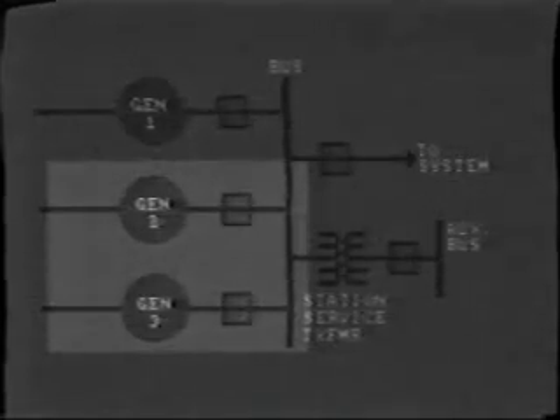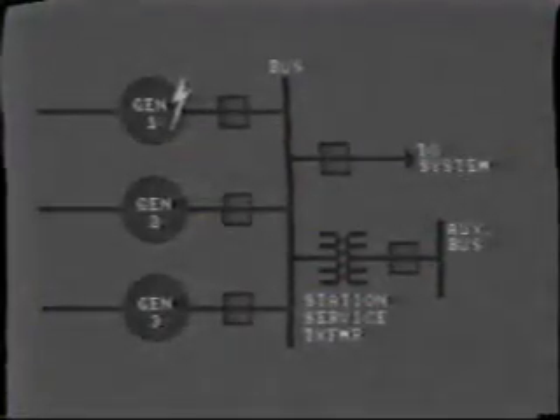Smaller generators are generally connected through the circuit breaker directly to a common bus. Several other generators may also be connected to this bus. The bus feeds the power system and also supplies the station service transformer, which provides power for the station auxiliaries. A fault occurring internally on generator 1 should be detected by its protection system, and this will cause its specific breaker to open and its own excitation system to de-energize.